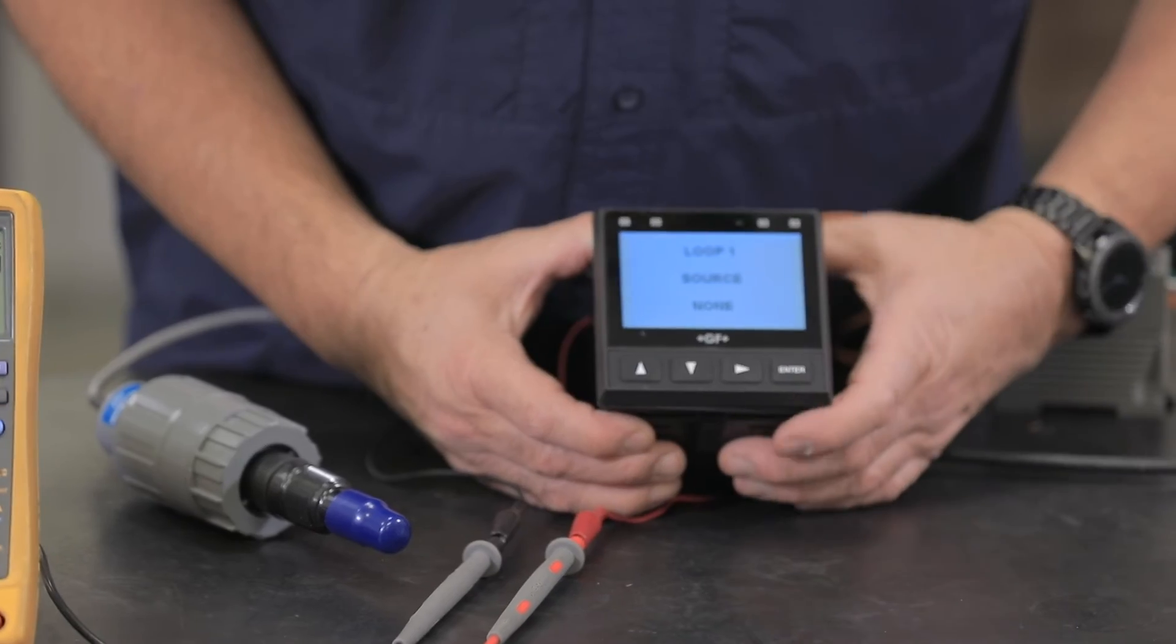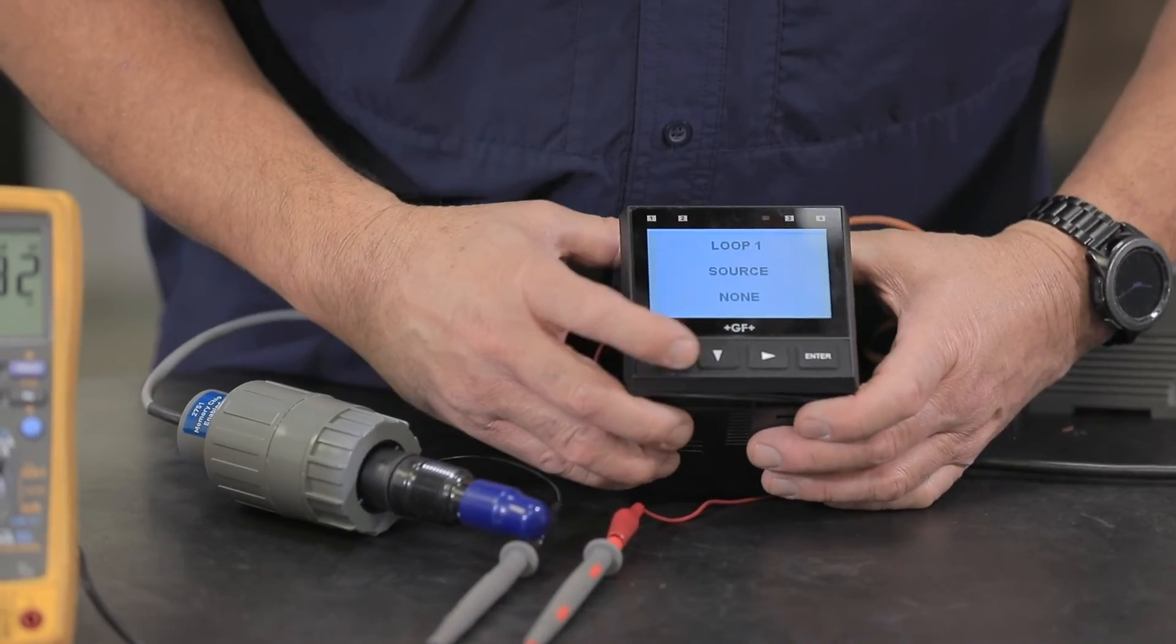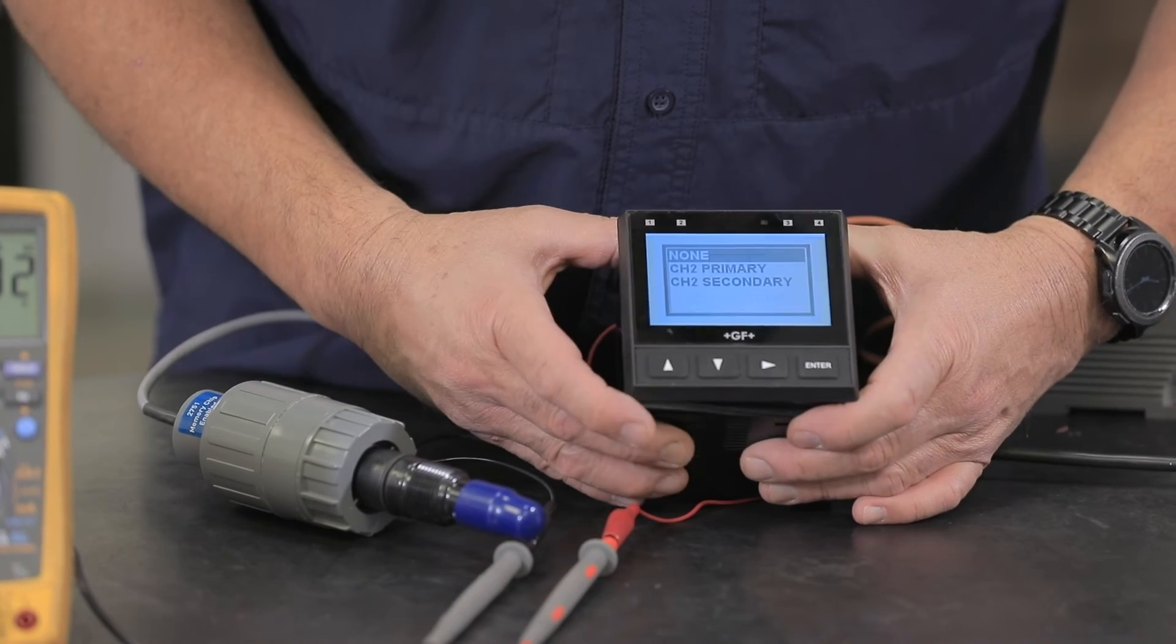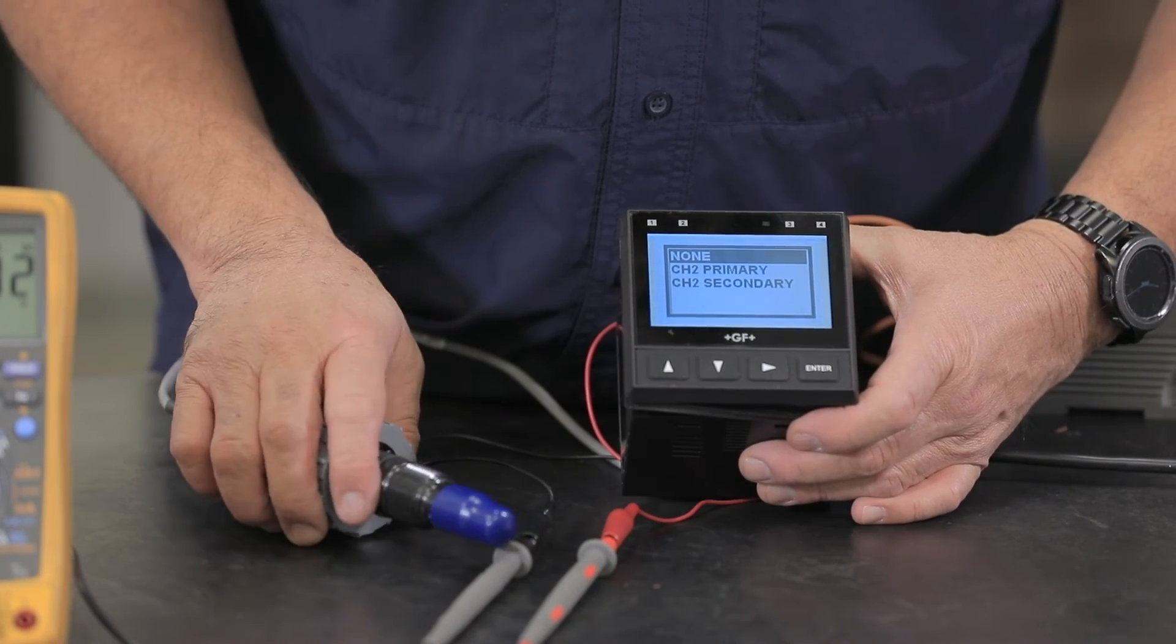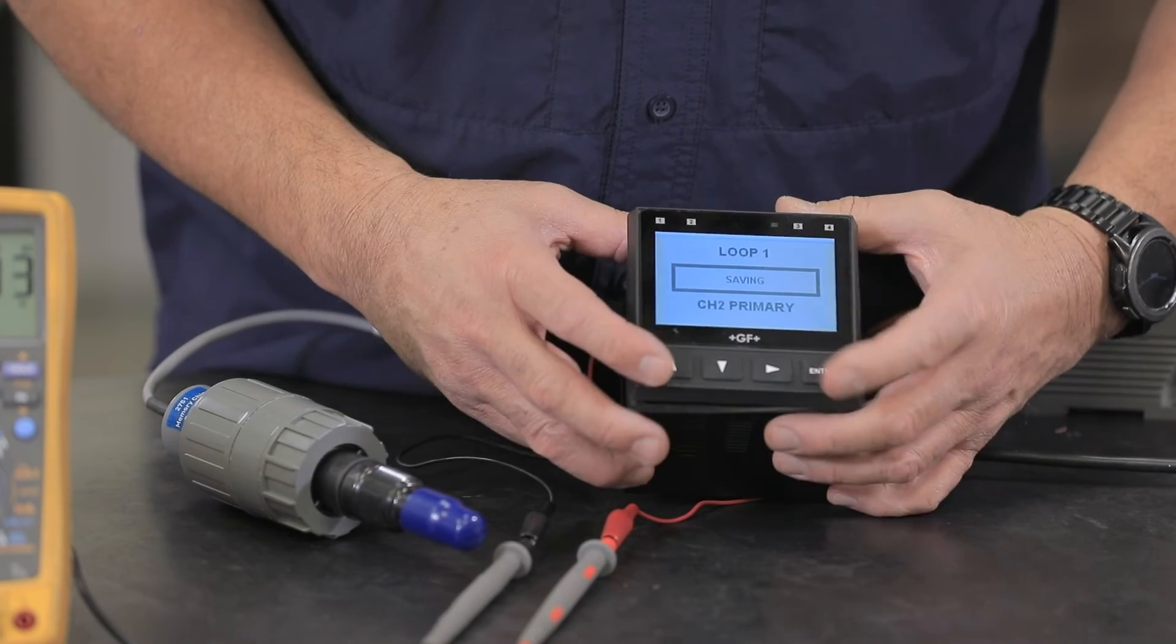Loop one source is none. We want loop one to be our pH, so we're going to choose with the right arrow, enter our code. We're going to choose channel two primary. Press enter. Save it.